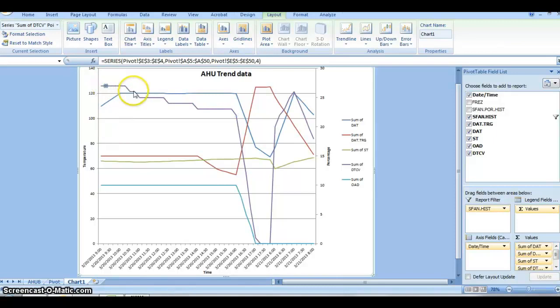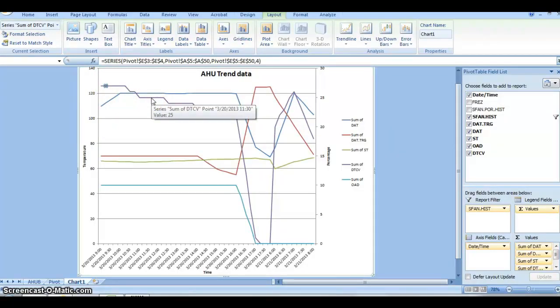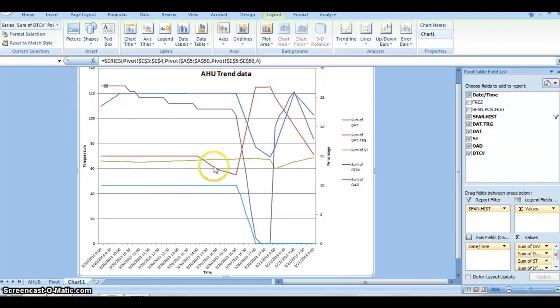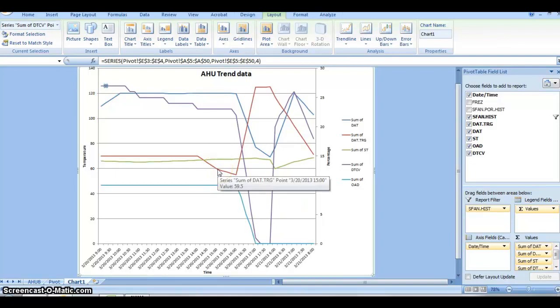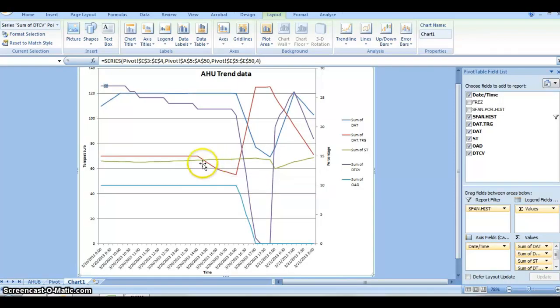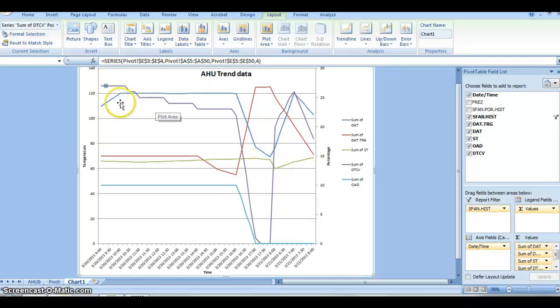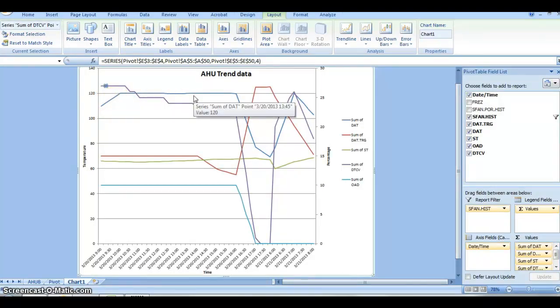This purple line here, we have the control valve, which seems to be modulating down as temperature tends to go up. That's a pretty steady temperature line, it's not fluctuating too much, so the temperature sensor is operating correctly. The discharge temperature is staying fairly high when it should be heating the building.